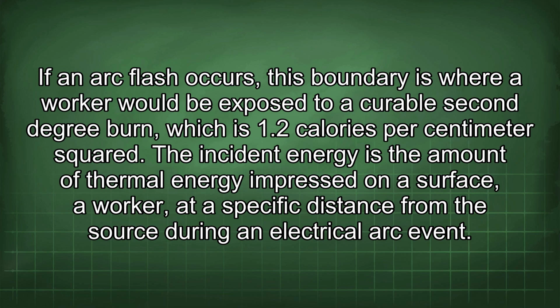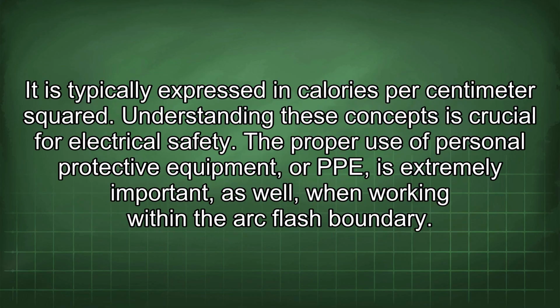The incident energy is the amount of thermal energy impressed on a surface, a worker, at a specific distance from the source during an electrical arc event. It is typically expressed in calories per centimeter squared. Understanding these concepts is crucial for electrical safety.